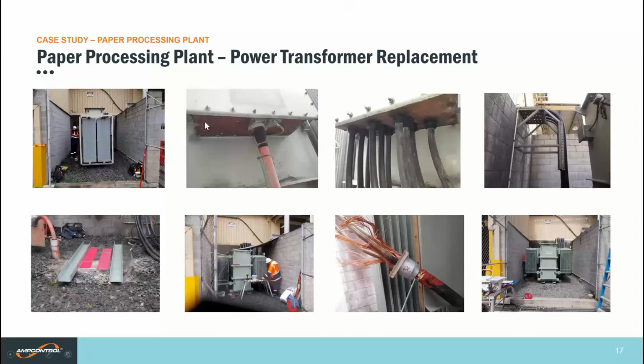Running through some photos from site for that case study. That's the original transformer. As you can see, it's quite high and fairly well packed into the location. This is the as found cable. Initially, it was assumed to be paper lead, but it turned out to be an XLPE cable. On the low voltage side of things, we had 300 square mils per phase. So again, fairly difficult to work with. The last photo on the top there was the existing 300 square mil cables coming in and up to the transformer. We had to do a little bit of modification to get them to suit the new transformer.